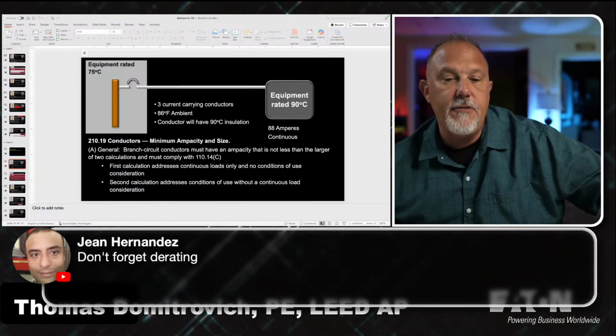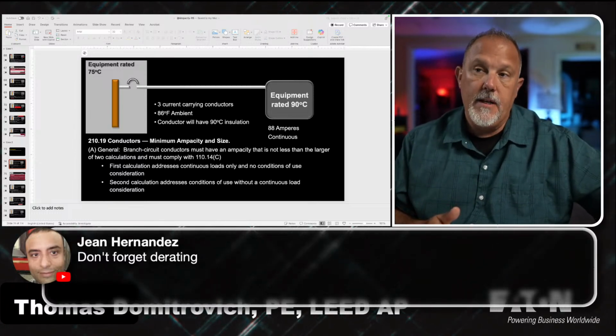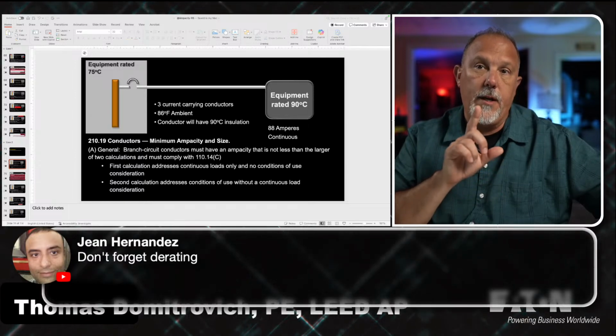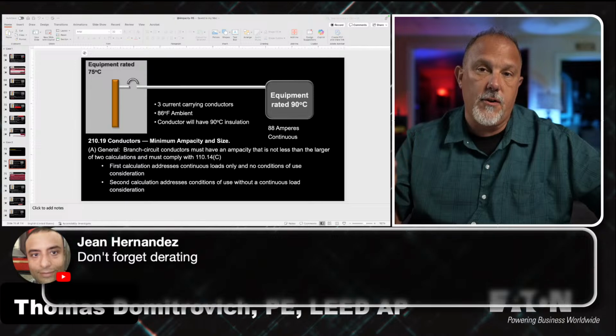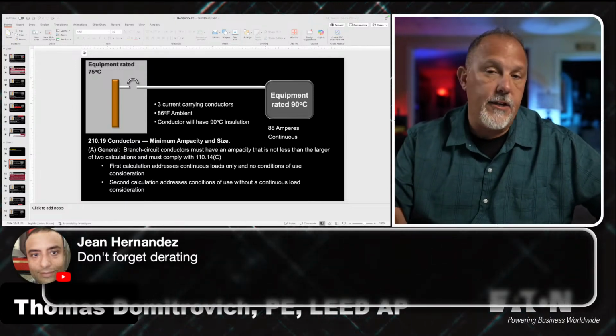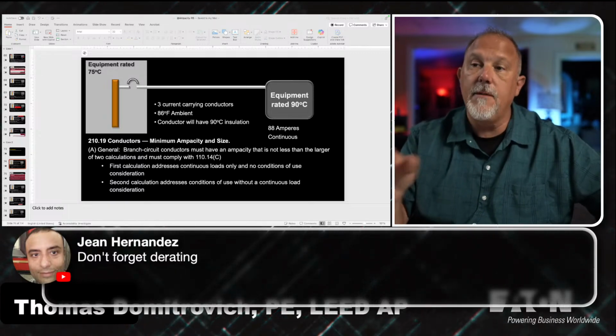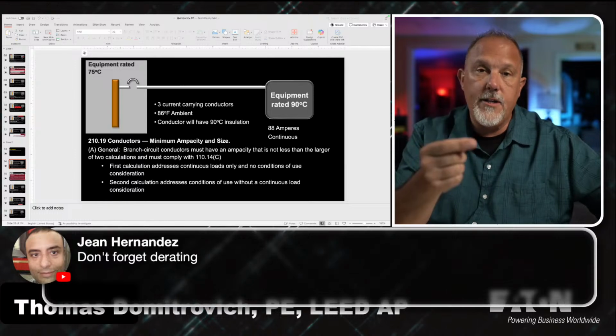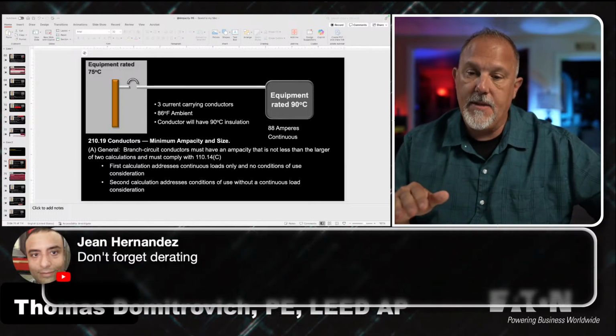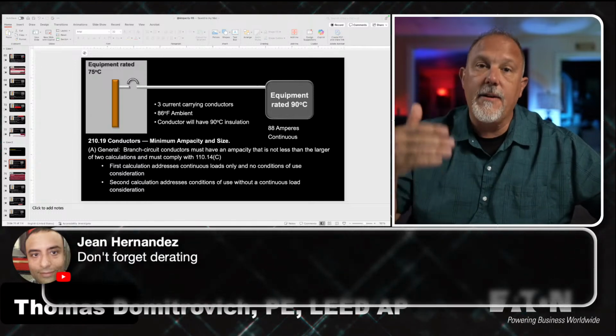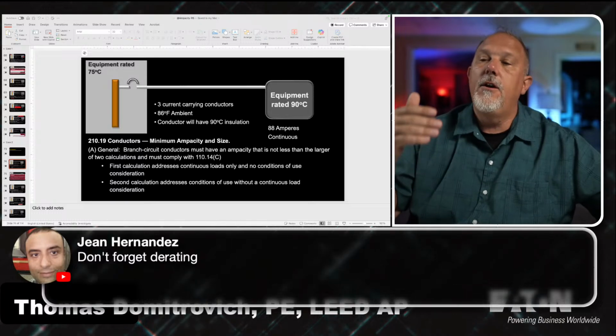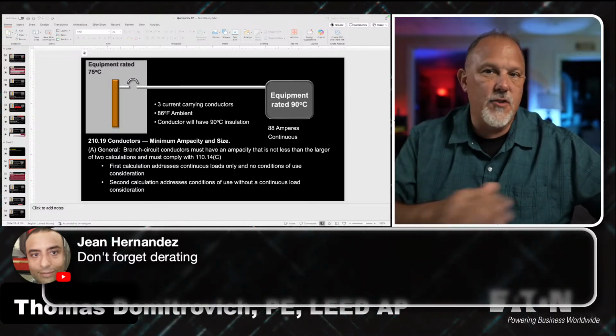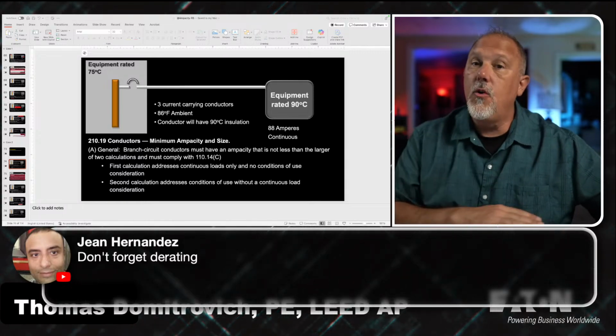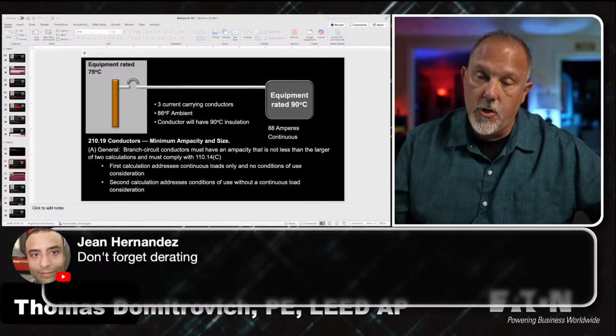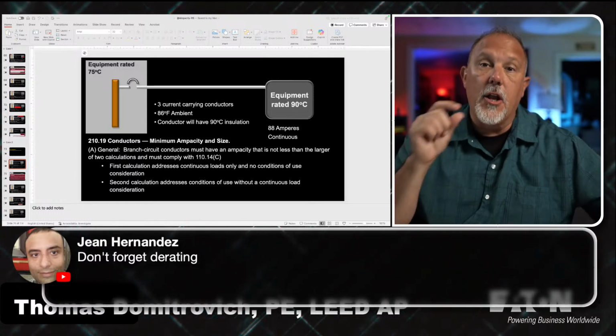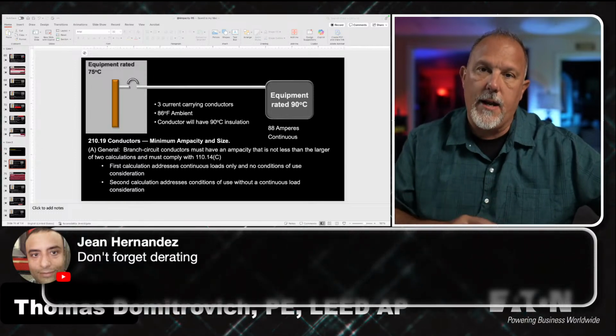Okay, Gene, it says don't forget derating. So, Gene, what we're doing is we're following the code, and we are following the requirements on how we determine the size of a conductor for the load. We're starting in 210. We know this is a branch circuit. I know I've got 88 amps. I'm going to do two calculations. One is not going to consider any adjustments to the ampacity. The other is going to be considering just the continuous loads. The first calculation is just continuous loads with no conditions of use applied. The second one is we're going to apply the conditions of use and we're not going to apply the continuous load. The larger of those two, whatever it happens to be, is what I'm going to select.